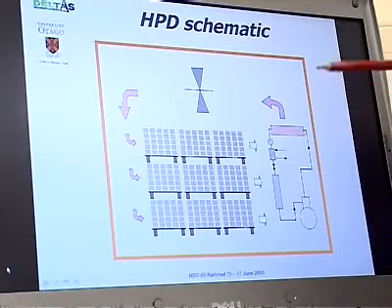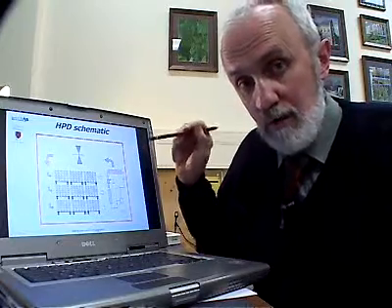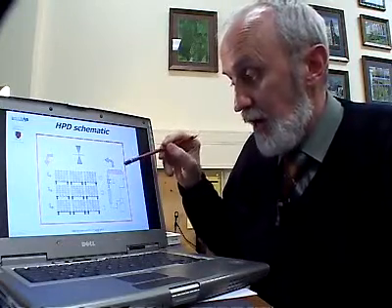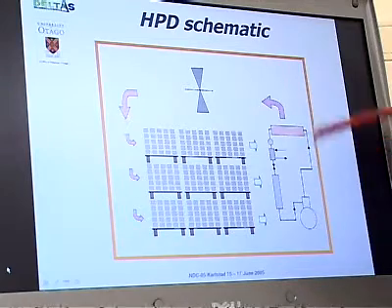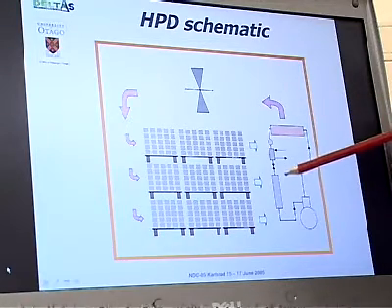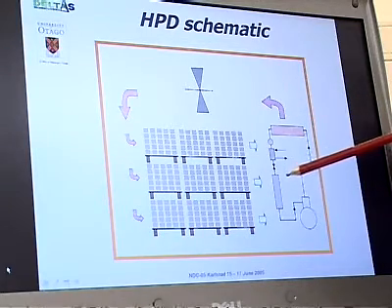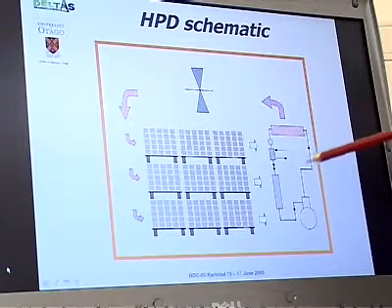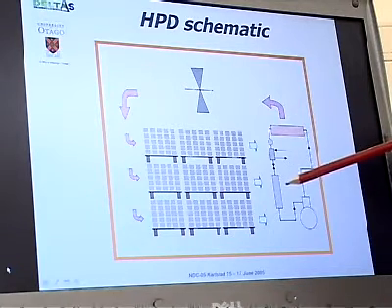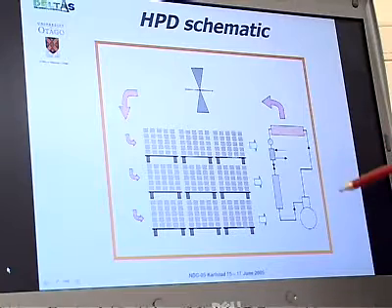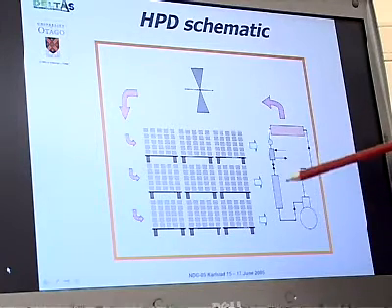The problems with designing something like this to make it work well are that unless this is cold enough to actually condense water out on the surfaces of that cold surface, unless it's cold enough, then you don't get very much moisture removed. But if you make it too cold, then the compressor down here has to do more work than you'd want it to.